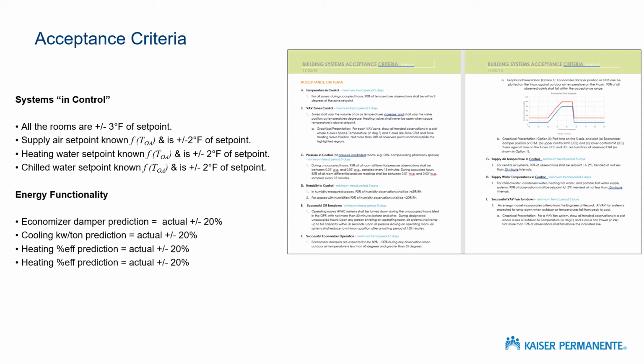So the first thing to think about is, what do we mean when we say the building is in control? If we just want to say this building is in control, and I'm using quotes around the words in control, what does that actually mean? Well, it shouldn't be that hard to define, right? All the rooms should be plus or minus 3 degrees of their set point. The supply air set points for the air system should be pretty well known. Those are typically a function of outdoor air temperatures, maybe something else. And the actual supply air should be plus or minus 2 degrees of that set point. That's in control.